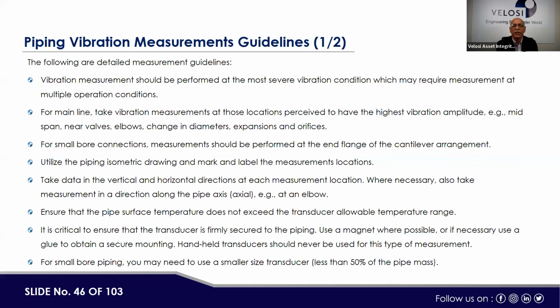Ensure that the pipe surface temperature does not exceed the transducer allowable temperature range. If we put a transducer on a high temperature line, it could be damaged. Then it is critical to ensure that the transducer is firmly secured to the piping. Use a magnet where possible, or if necessary, use glue to obtain a secure mounting. Handheld transducer should never be used for this type of measurement. Normally it is handheld, but the problem is the probe of the transducer should be properly fitted with the piping system. Just as we do normal UT gauging, for small bore pipes we use a micro probe. Similarly, we need to use a vibration measuring tool which can have a proper grip on the pipe with respect to its diameter.